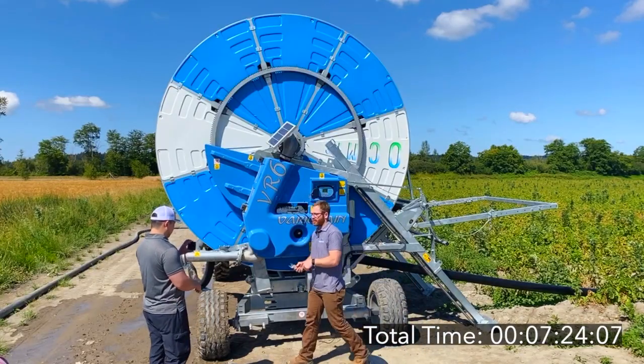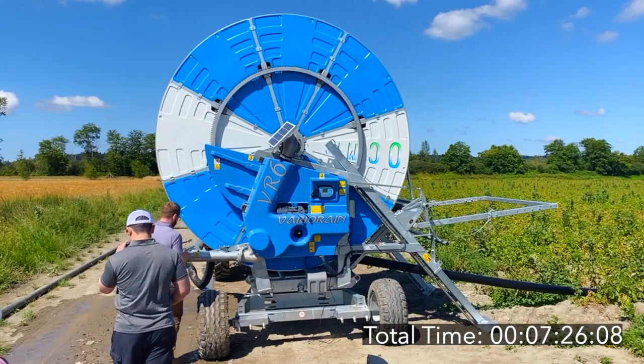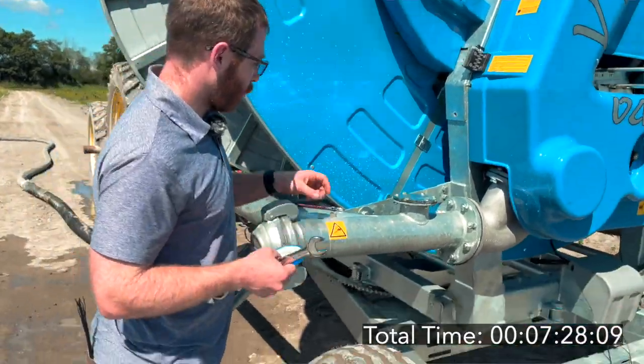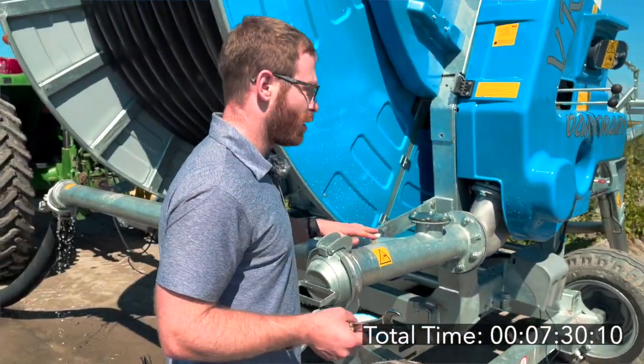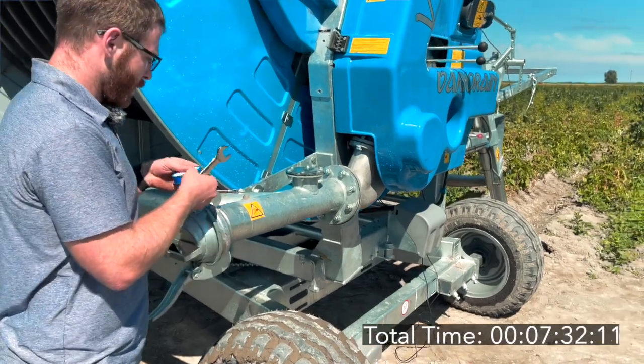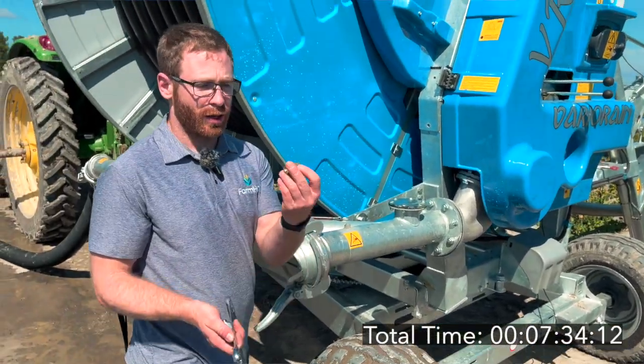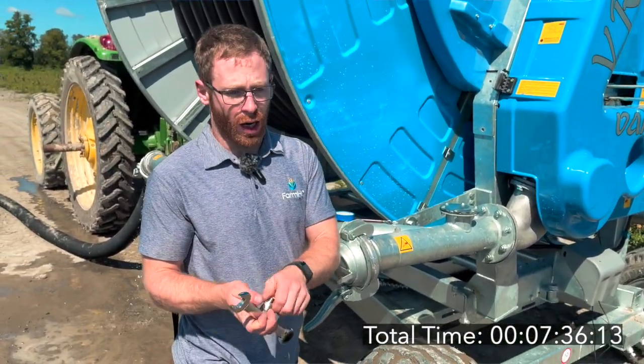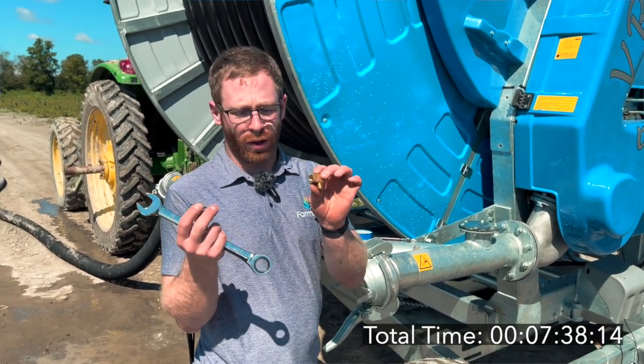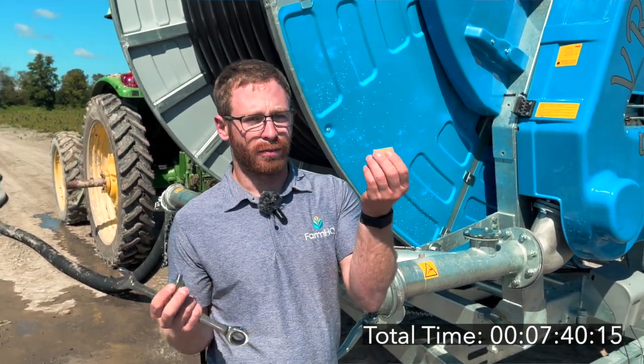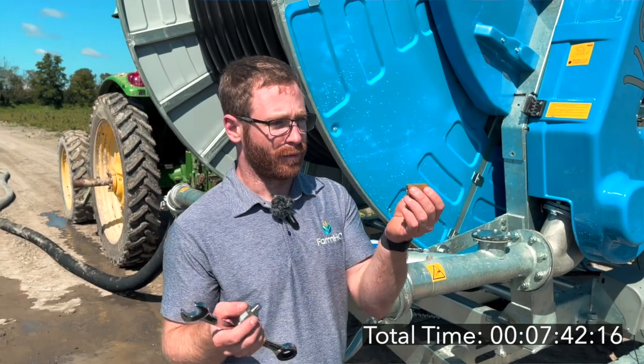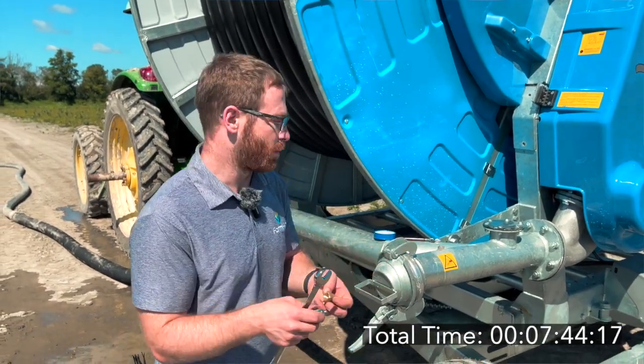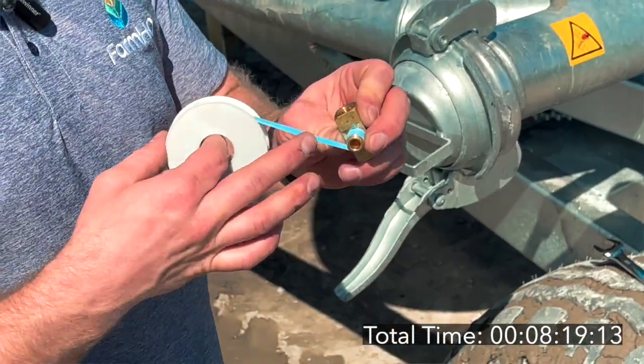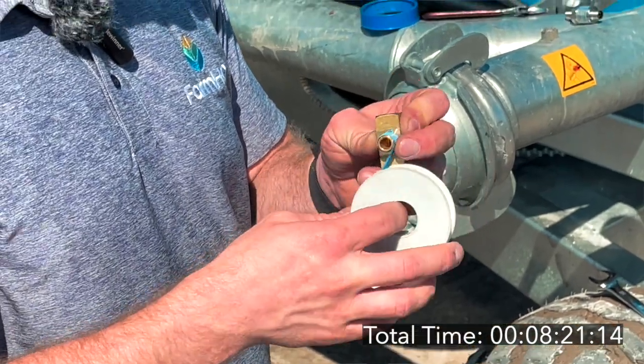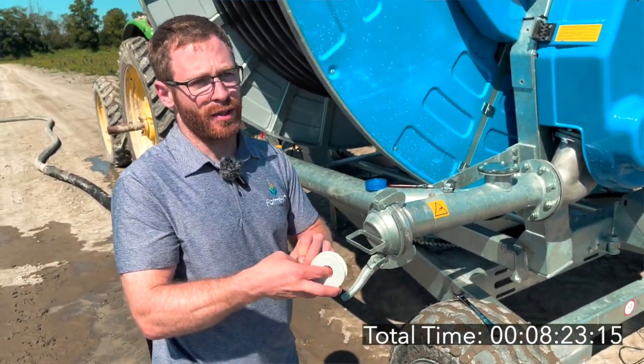Next is mounting the pressure sensor. I pulled the old pressure sensor out of the old port, and I'm going to put in a T, then mount our pressure transducer and the old pressure gauge in place, instead of just having the pressure sensor as before. I'm putting a little Teflon tape on the threads, which is a pipe thread sealer.